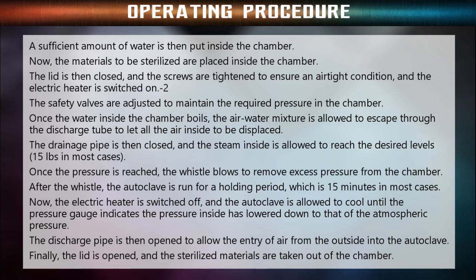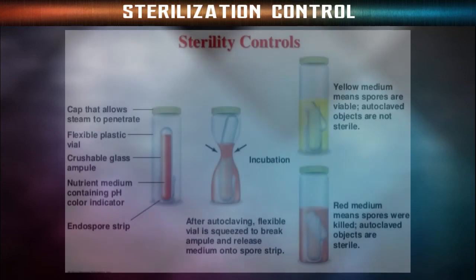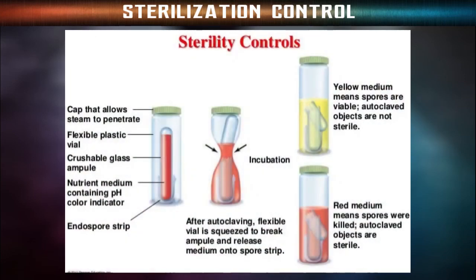Now the electric heater is switched off and the autoclave is allowed to cool until the pressure gauge indicates the pressure inside has lowered down to that of the atmospheric pressure. The discharge pipe is then opened to allow the entry of air from the outside into the autoclave. Finally, the lid is opened and the sterilized materials are taken out of the chamber gently. Coming to the sterilization control, modern autoclaves have devices to maintain proper pressure and record internal temperature during operation. Regardless of the presence of such a device, autoclave pressure should be checked periodically and maintained.